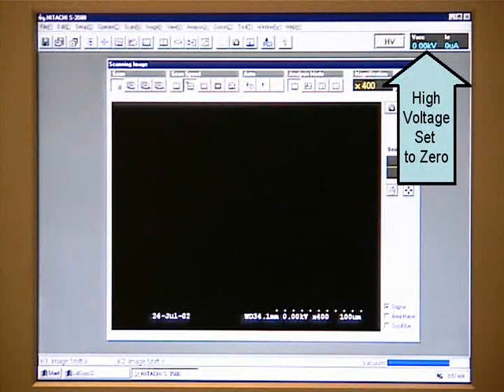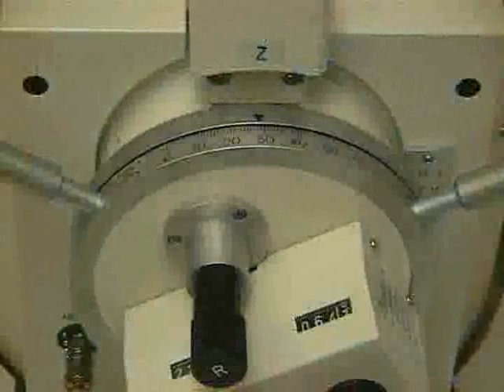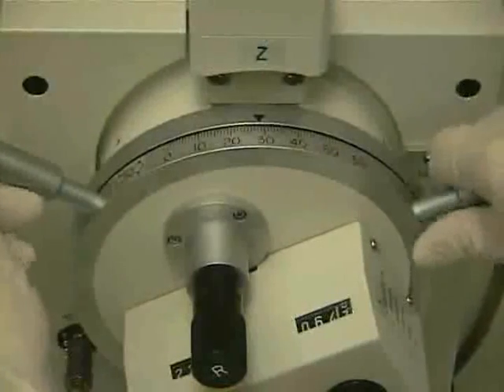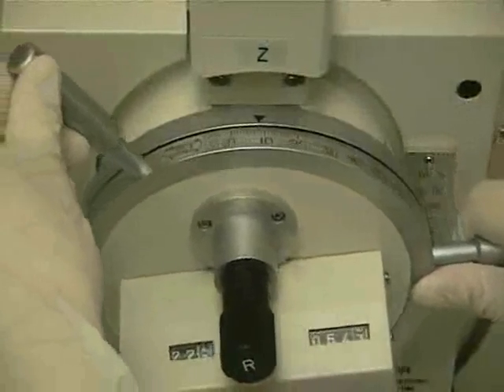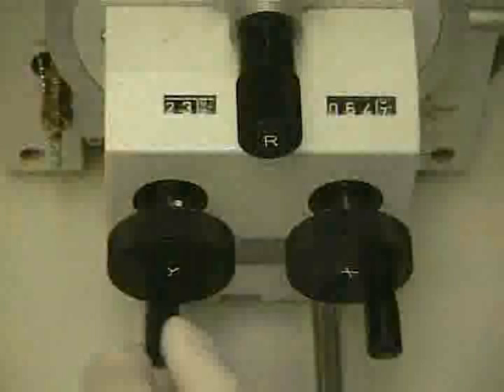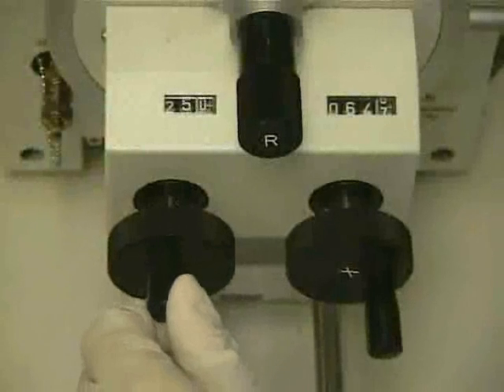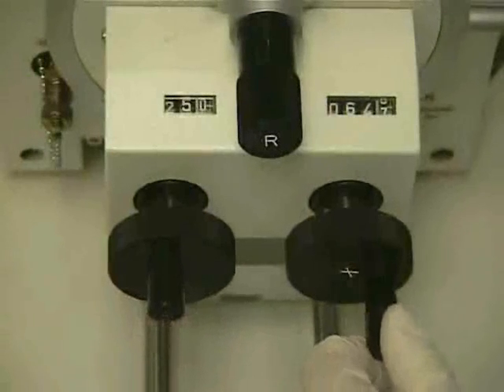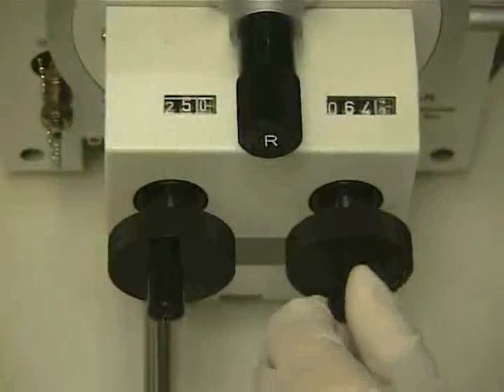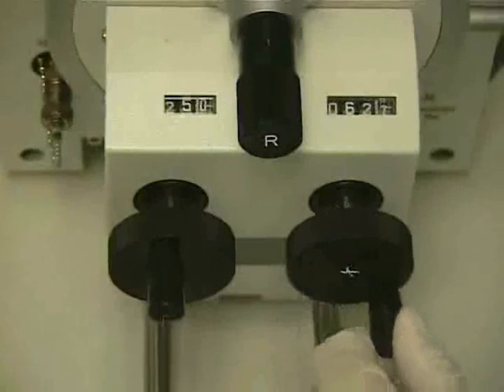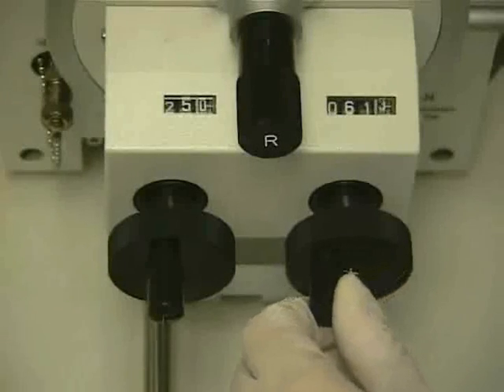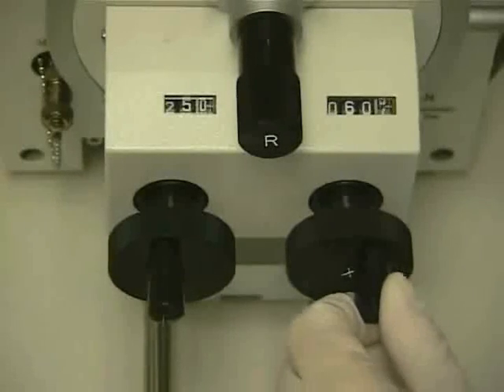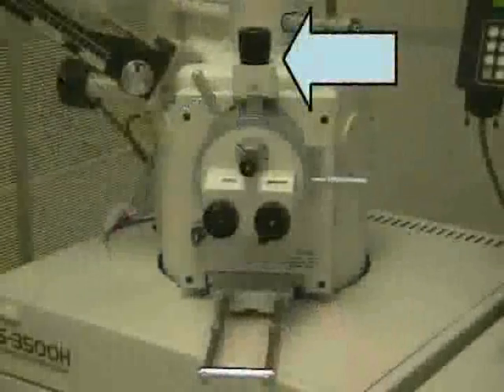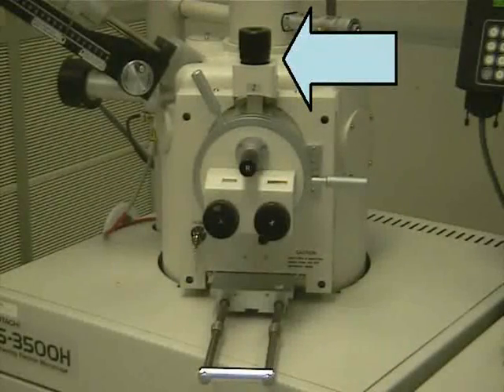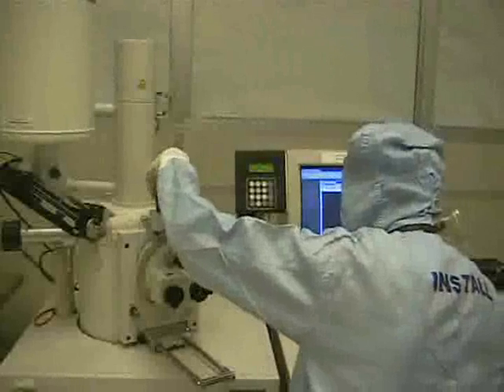The software is now initialized, and we must now make sure that the hardware is set properly. We need to make sure the stage inside the chamber is set to the loading position. The loading position has a tilt set to 0, the y-axis set to 25, and the x-axis set to 60. We then adjust the Z position so that the black arrow is pointing to 30 on the black numbers or 25 on the red numbers.